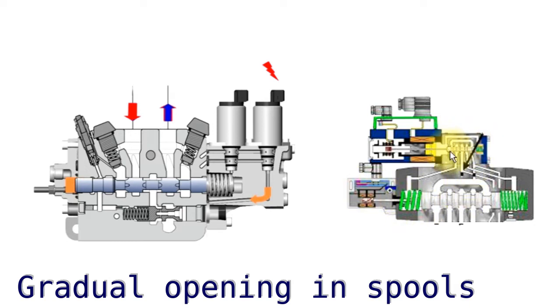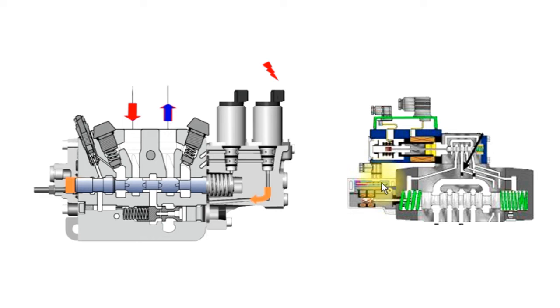This is quite a complicated valve. We've got a pilot up here controlling the pressure on either end of the spool and the position of the spool, and then we'll have a position feedback. So there's a lot of electronics here making sure we very accurately control the position of that spool. So we're going for accuracy in industrial very often.